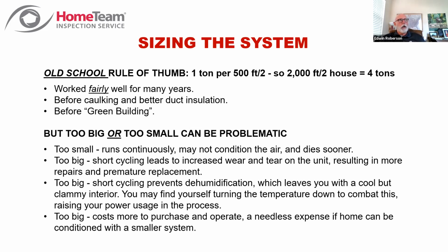Could be too big. In fact, we had one just this past summer that we walked in. That was our first sensation, and we asked some questions, and we had some other issues with the crawl space and all that kind of went to the overall. But sure enough, that was one of the really big hits: that system was just sized wrong. The HVAC guys confirmed that. Again, too big is just going to cost more to purchase. Bigger equipment's going to cost more, and it's also going to cost more to operate it. So, needless expense if you don't need something that big.